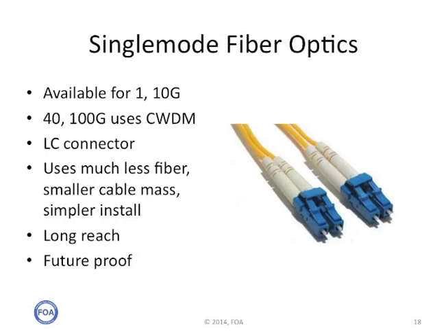Single-mode fiber has practically unlimited bandwidth and distance capability when used in data centers. Unlike the parallel 10 gig channels used with multimode fiber, single-mode fiber uses coarse wavelength division multiplexing to transmit multiple channels over one pair of fibers at different wavelengths. Thus, 100 gig is achieved using 4 25 gig wavelengths over only 2 fibers, greatly simplifying fiber installation and management.